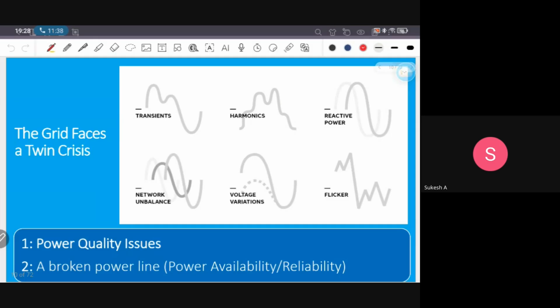The EV charging challenges manifest as two interrelated crises. The first one is the power quality crisis, the fitness of electricity. Power quality is the fitness of electricity, how pure the sinusoidal waveform is. We know there won't be a 100% sinusoidal waveform if we are using power electronic equipment or static devices, but we are smoothing it, maximizing the quality of the AC voltage waveform to reach a sinusoidal waveform. But we are facing transients, harmonics, reactive power, network unbalance, voltage variations, and flicker. These are the main power quality issues we face with the involvement of power electronic devices. But luckily, power electronics is the reason for these power quality issues, and power electronics is also the remedy for reducing them.